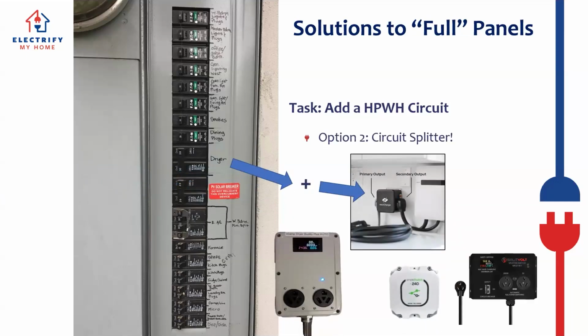Another great option, which alleviates both space issues and panel capacity constraints, is circuit splitting. We do this all the time. A circuit splitter takes an existing 240 volt circuit from the panel and splits it into two, ensuring only one will run at any given time so we never exceed the allotted capacity of that breaker. For example, we can put a dryer on one side and an EV charger on the other. We have this example for a heat pump water heater too, though we try to avoid installing heat pump water heaters on a circuit splitter if possible, because of the need to always have hot water. But in some situations we've done so with great success, and there are several products on the market now that make this really easy to do.